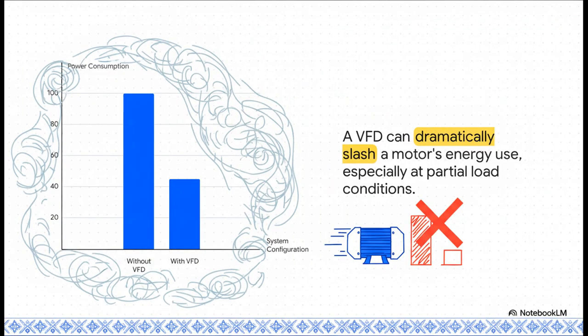And this chart shows you exactly why this is a big deal. The energy savings aren't just a little bit here and there. They are huge. A VFD can slash the energy use of a motor, especially because most of the time, systems are running at partial load.